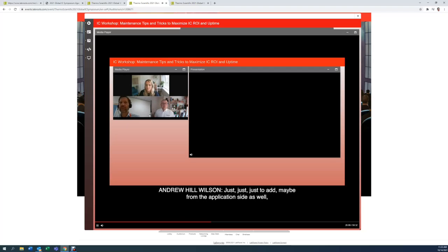Yeah, I think just to add maybe from the application side as well, one of the things we often advise is also just to really look for trends. So when your system was installed and you first set that application up, make a note of where that chromatogram was when you first ran a standard, when everything was new and you first developed the application. So you've got something to compare to, because as Andrew said, things will vary a bit over time. But if you've got something to always refer back to, you've got a benchmark.